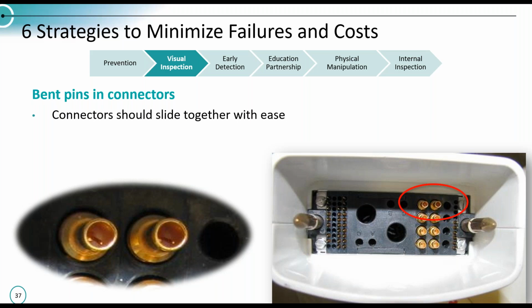You want your end users, before they plug the coil in, to take a look inside the connector, maybe using readers or a magnifying glass to look at the coils and the pins inside the connector. If a pin is bent on the connector side, there's a damaged complement to that on the MRI scanner side, and you'll end up with intermittent connections on almost any coil plugging into that magnet. You want the connectors to slide together with ease, and you want to inspect the connectors for bent pins.